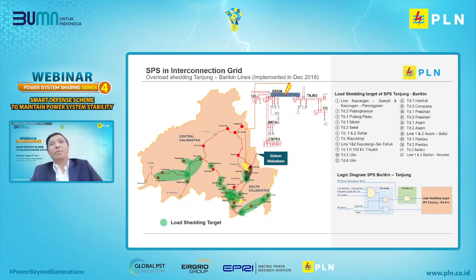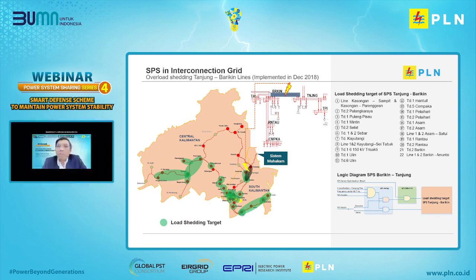This is the second SPS in the interconnection grid in Kalimantan. The first in interconnection, the second in Kalimantan. We can see on the screen that the most highly loaded area in the interconnection system is in South Kalimantan, while the power plants are mostly located in East Kalimantan. So to meet the power demand, a transfer is required through the Barikin Tanjung transmission line with a maximum power transfer of up to 250 megawatt.